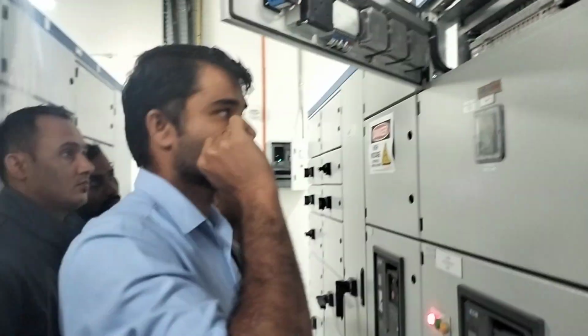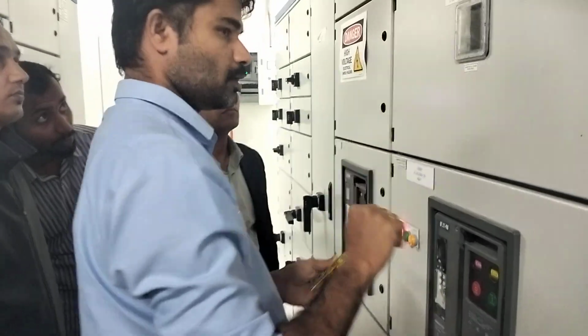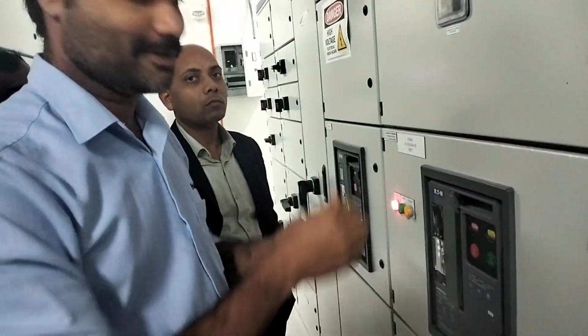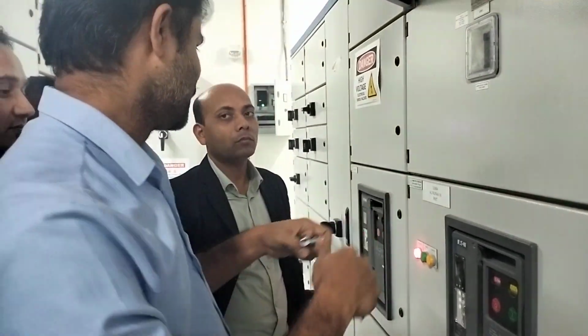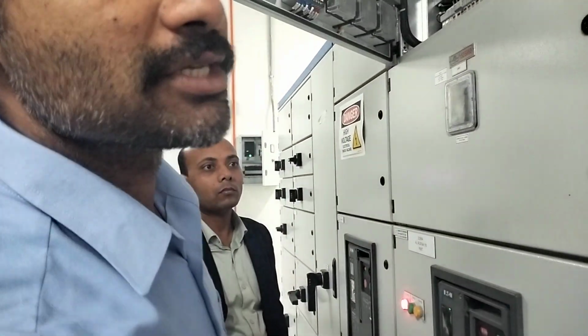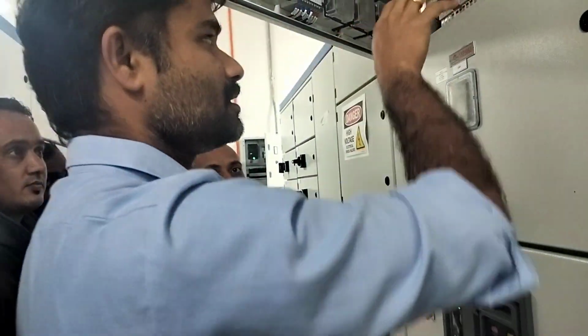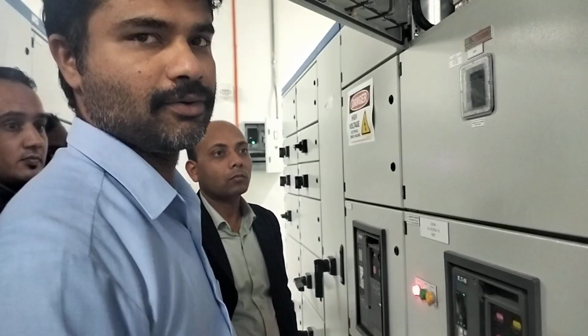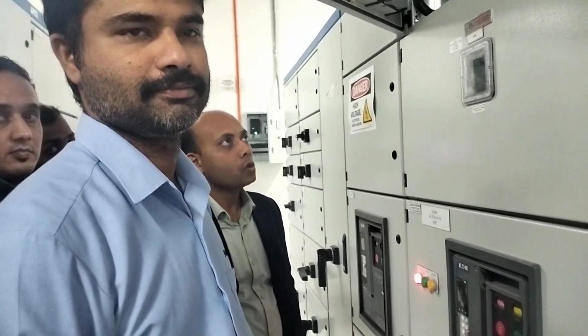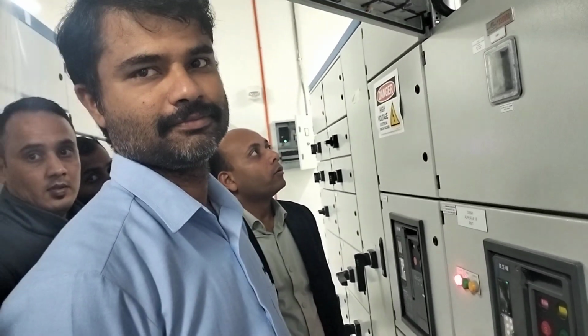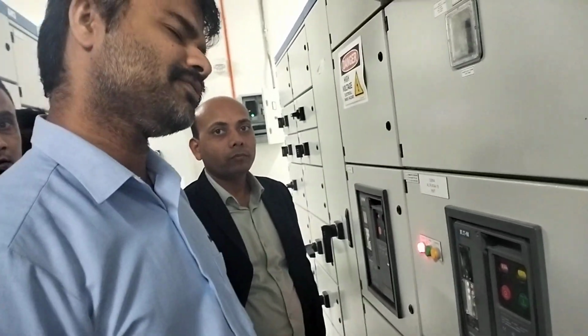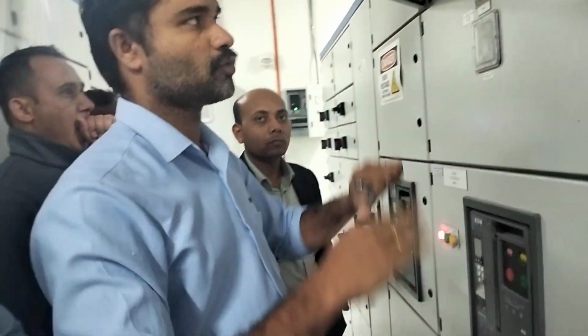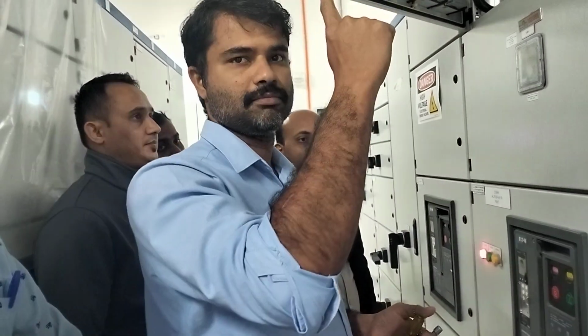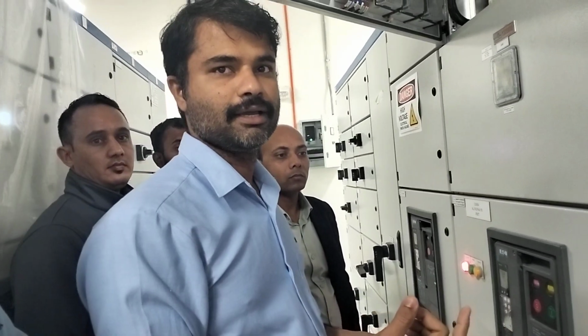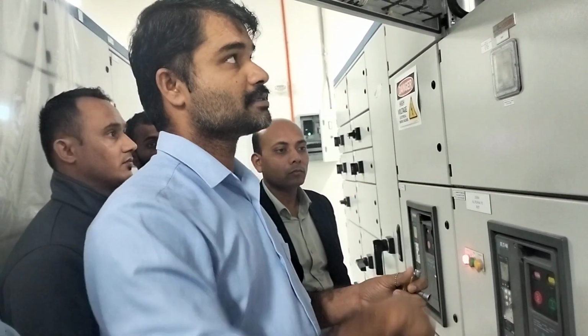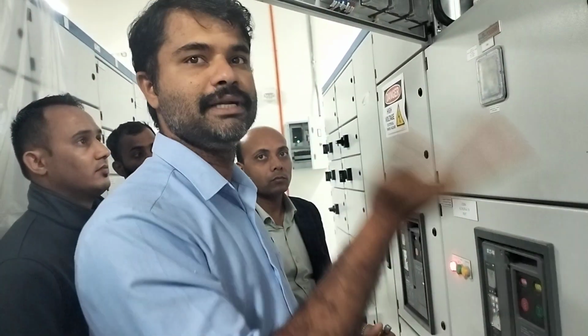So you just come and reset. Just take the fuse in and out. Don't do it now, because it will start the generator and it will cut off. Make sure it's in manual first. Then reset it, and then you can keep it back in auto. Normal fluctuation or under voltage happens everywhere. Sometimes the generator will start. Sometimes a sudden fluctuation will come and it will clear immediately.